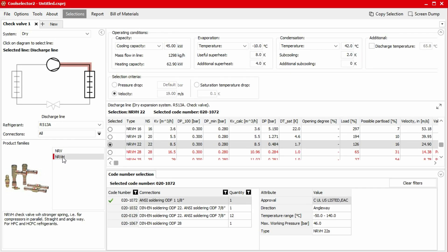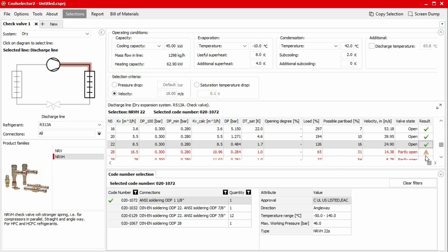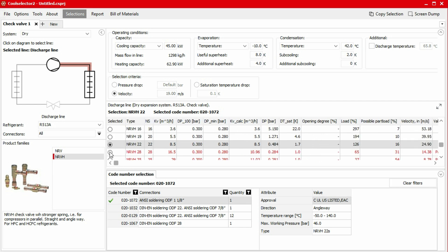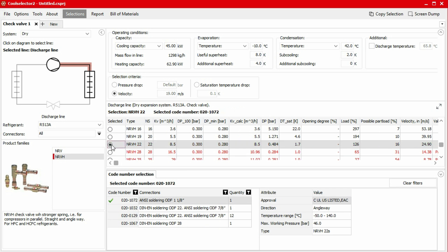The window will now refresh to show the space and product information. For the selection criteria, we can choose between pressure drop and velocity. For this example, I'll use velocity and leave the values as default. The table now shows a list of available products. Some products have red text — this is warning us that there is a compatibility issue with our system. We can view the warning by hovering our mouse over the warning symbol in the rightmost column. Additionally, a warning message will display above the table if we select the product. You will notice that one row is highlighted in green — this is the suggested product. This is only a suggestion and you should check the performance details to ensure it suits your system and requirements.